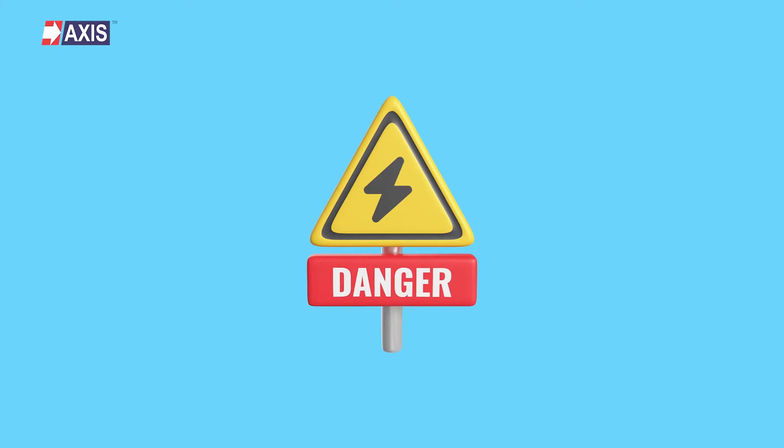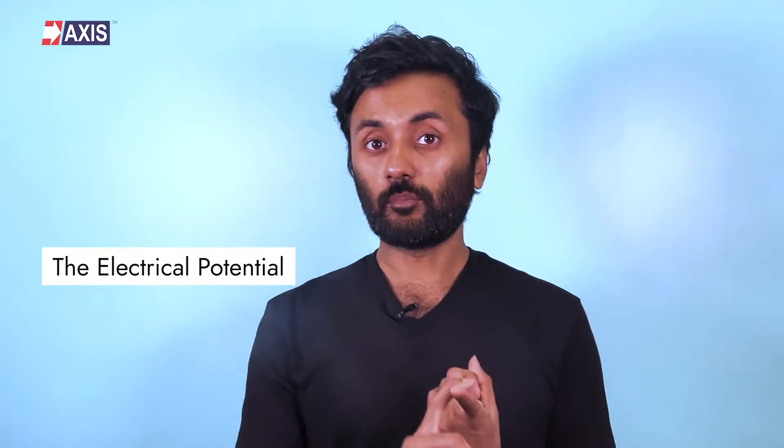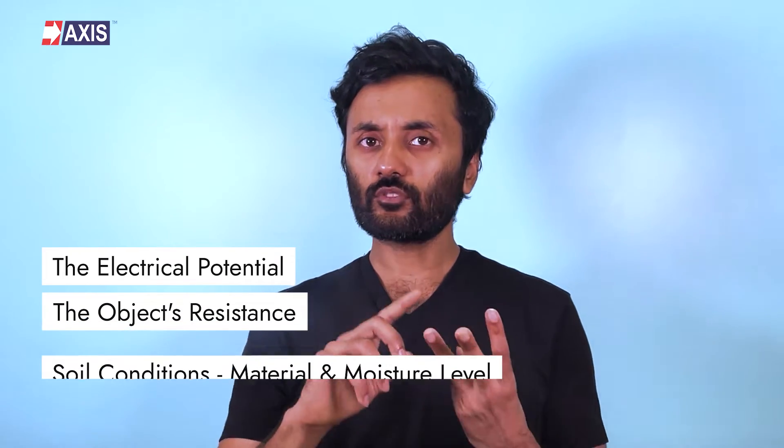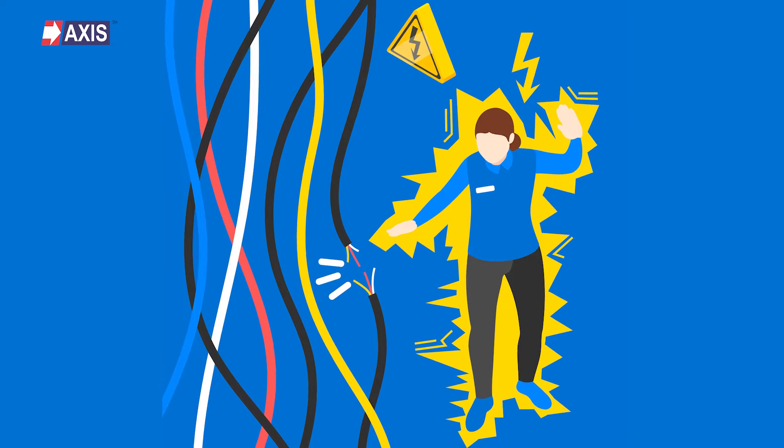So what happens if an energized wire falls onto a chain-link fence or directly into the ground? The object and its surrounding area will become electrically charged, creating a high voltage zone. However, the actual voltage level depends on a lot of factors such as the electrical potential, the object's resistance, and soil conditions including material and moisture levels. If a person or animal accidentally comes into contact with this high voltage zone, the result could be fatal or cause severe injuries.